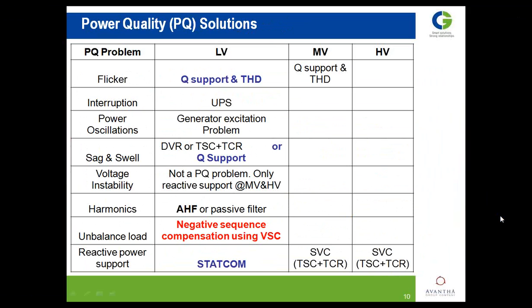If I summarize with respect to the classes of LV, MV and HV, these are the problems: flicker, interruptions, power oscillation, sag and swell, voltage instability, harmonics, unbalanced load, and reactive power. And if you look at the respective solutions, for LV, where the panel has covered most of it, it is basically either Q support, THD solutions, DVR, or generator excitation, mostly. Active and harmonic filters, both active and passive. Negative sequence and neutral current solutions. Unbalancing, and StatCom and whatever else is there for low voltage.